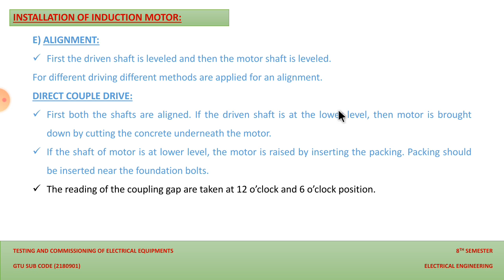If the motor shaft is at a lower level, then the motor is raised by inserting packing. Here we can insert packing of gasket as well as metal strips, and the packing should be inserted near the foundation bolt so that it will not get worn out in future. The readings of the coupling gap are taken at the 12 o'clock and 6 o'clock positions.